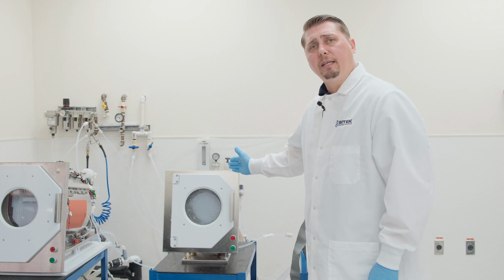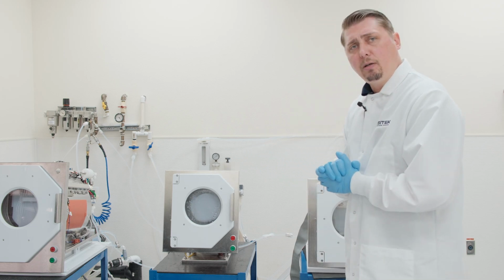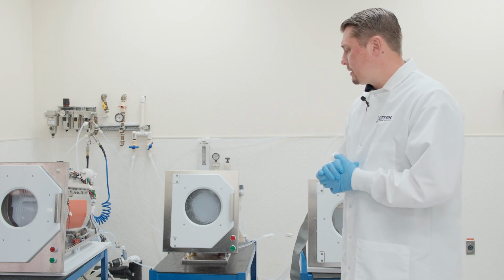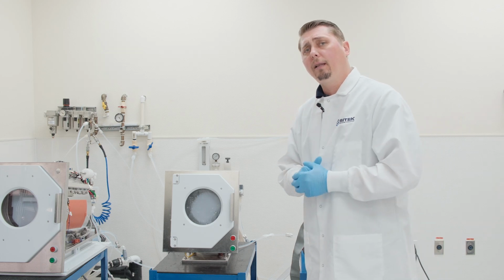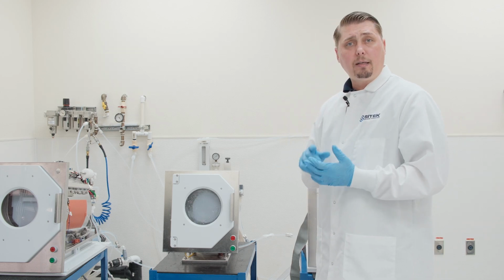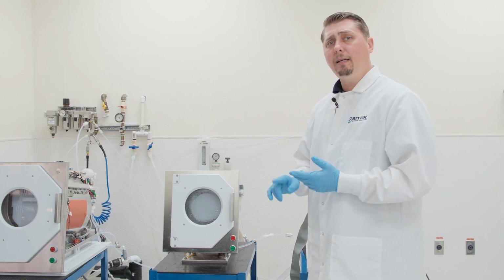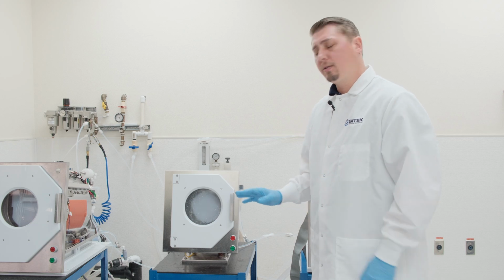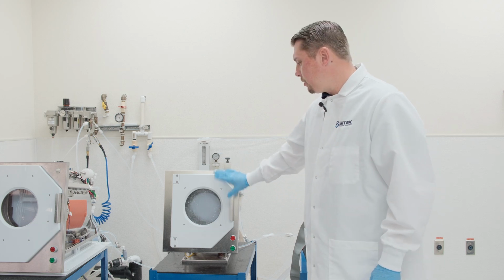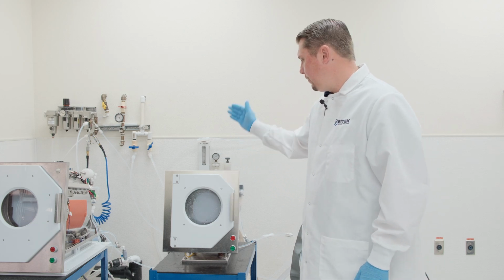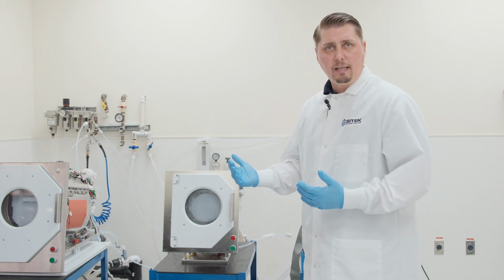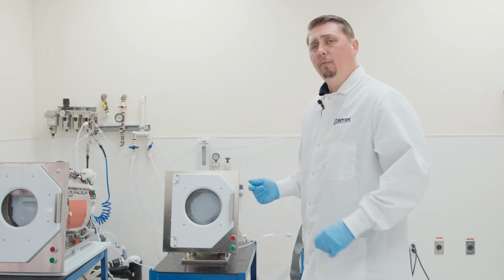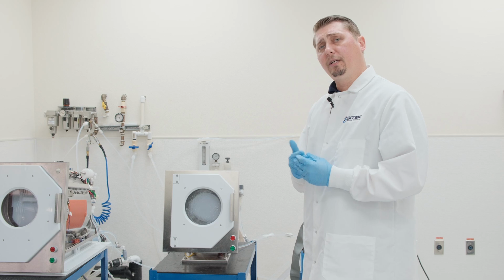Any refurbishments that come through Sitek will go through the same extensive refurbishment process. First, we break down the unit to the component level, then check to make sure all components are working correctly, clean and electropolish all metal parts, replace all consumables such as the seal, windows, N2 filter, tubing, etc.